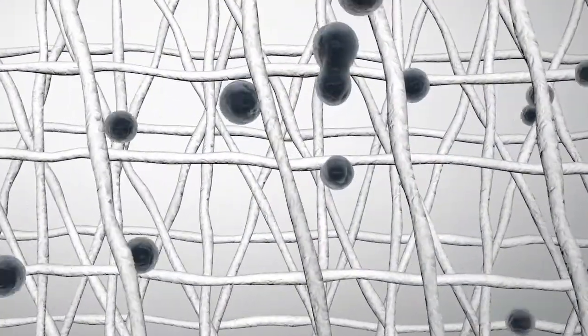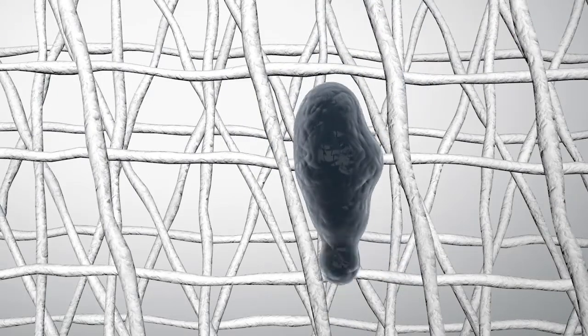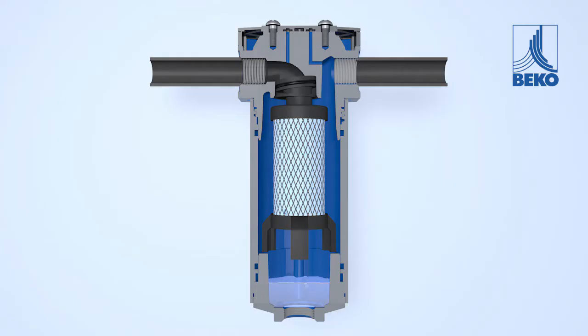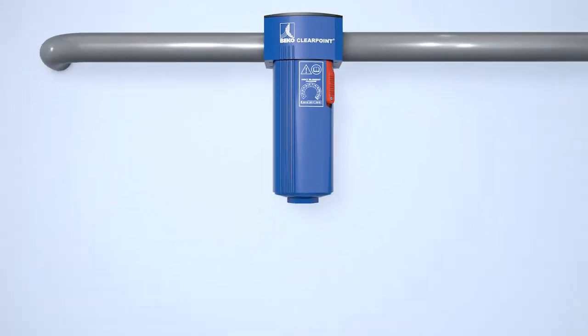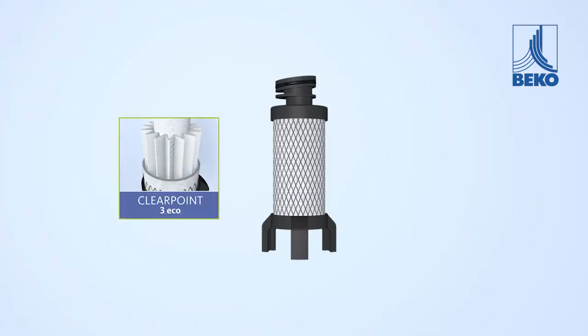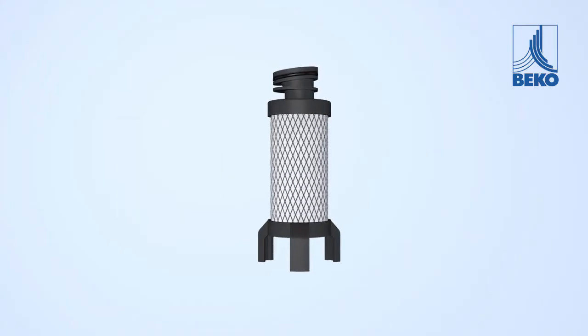Due to Brownian motion at a molecular level, the smallest aerosols collide with the fibers and are carried along in the flow direction of the compressed air to the fiber outer wall, where they join to form larger droplets. The resulting droplets are concentrated in the drainage layer of the wet, saturated filter and pass into the less turbulent collection chamber of the filter housing. This accumulated compressed air condensate can then be drained out, for example with the BEKOMAT condensate drain.